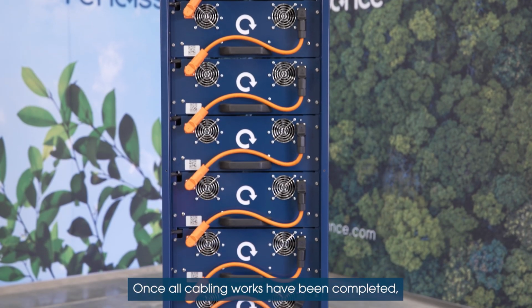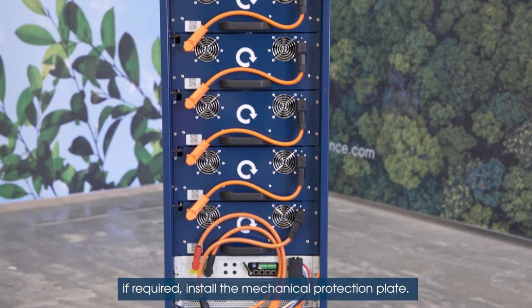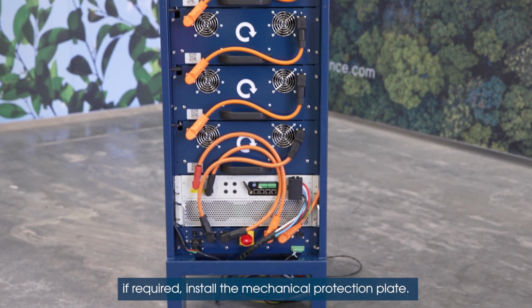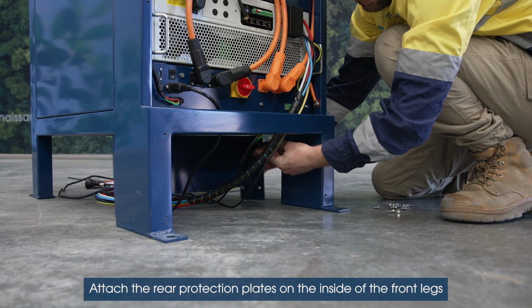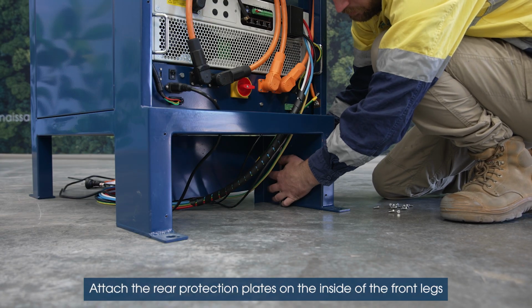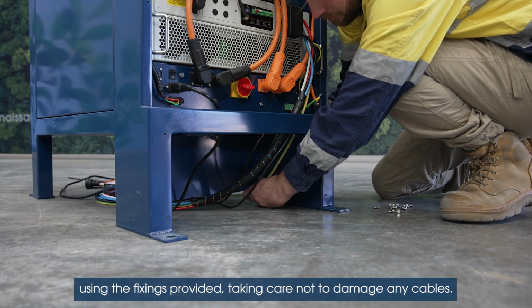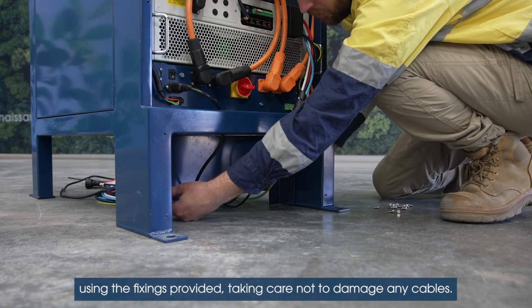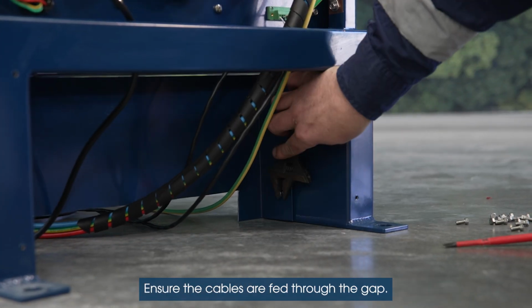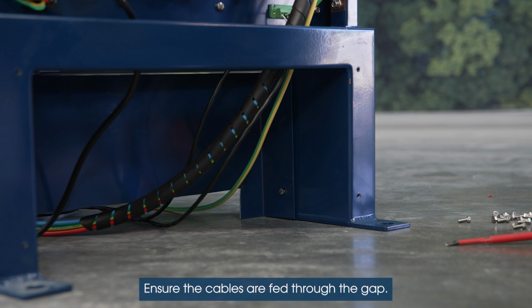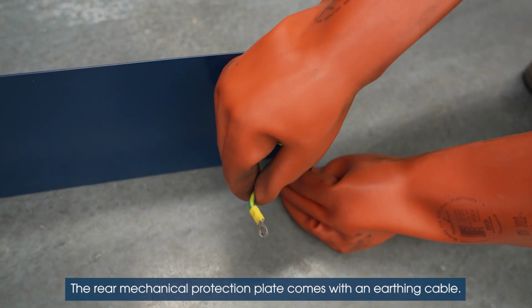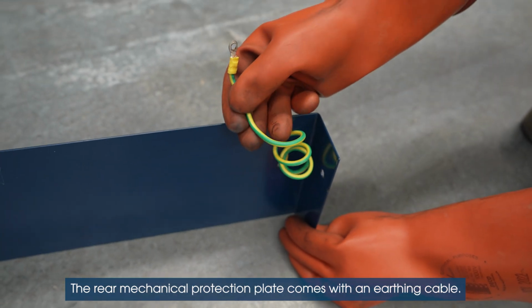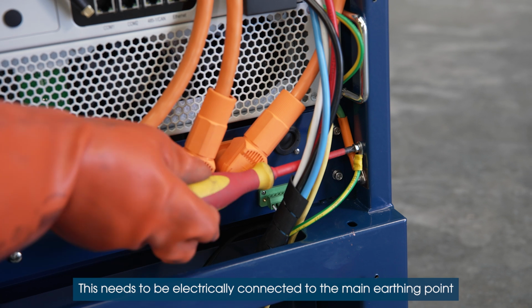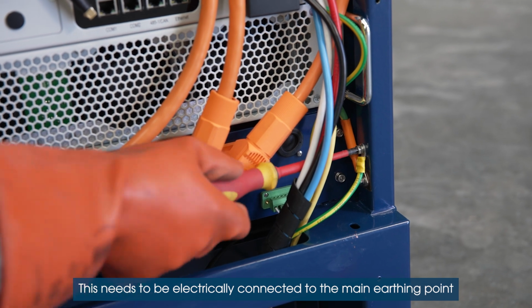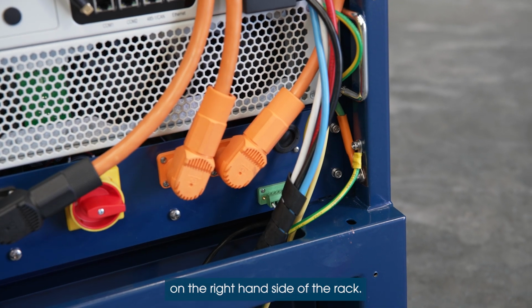Once all cabling works have been completed, if required, install the mechanical protection plate. Attach the rear protection plate on the inside of the front legs using the fixings provided, taking care not to damage any cables. Ensure the cables are fed through the gap. The rear mechanical protection plate comes with an earthing cable. This needs to be electrically connected to the main earthing point on the right hand side of the rack.